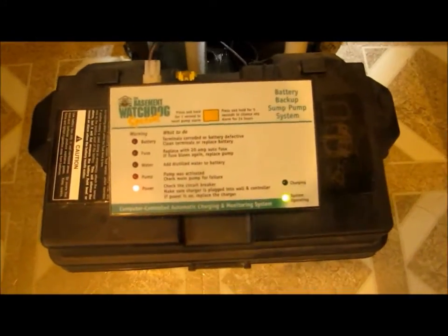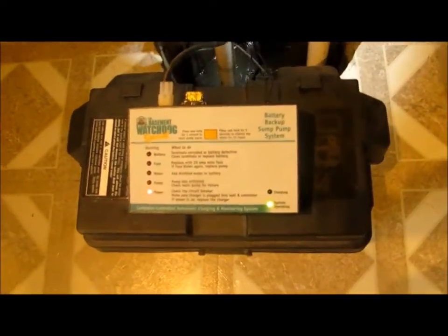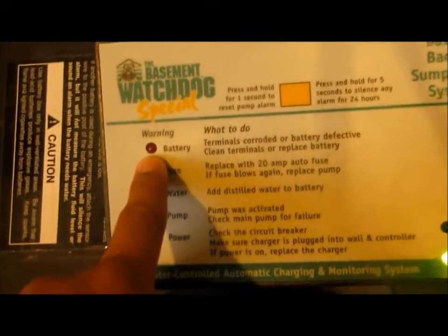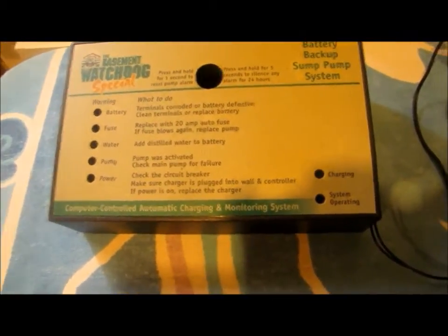This is my new control unit — this is what I call the newer generation. It specifically comes with a dual flow switch and some other features dealing with the alarm. What I do know is if the battery alarm comes on, you cannot silence it at all, compared to the older control unit which I have here — if the battery alarm comes on, you can silence it for at least 24 hours.